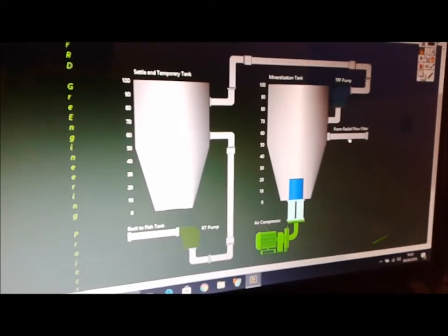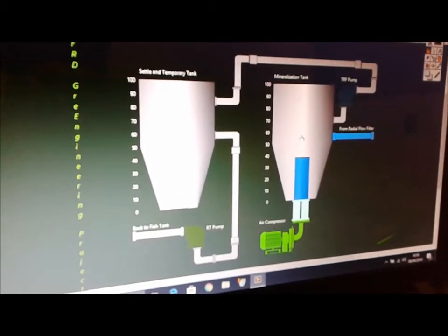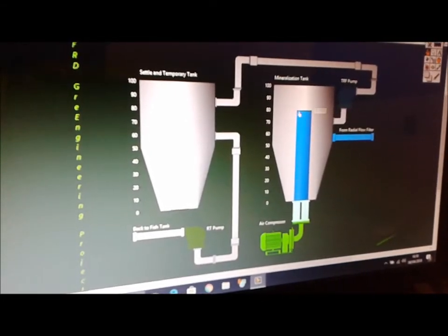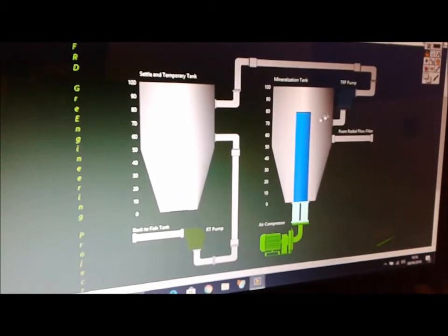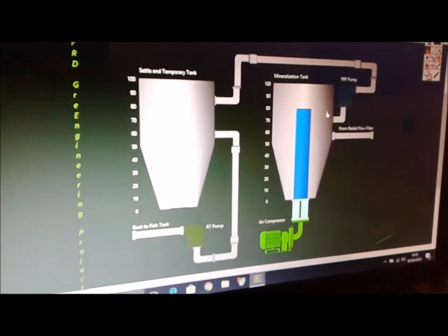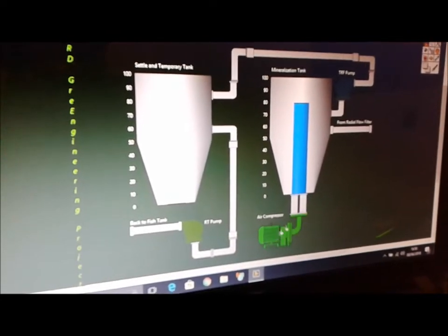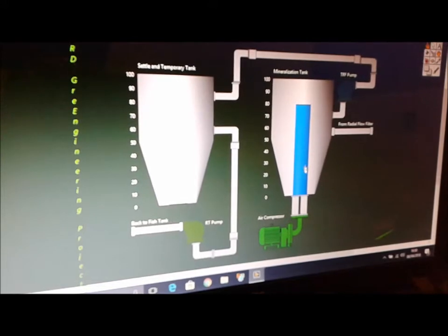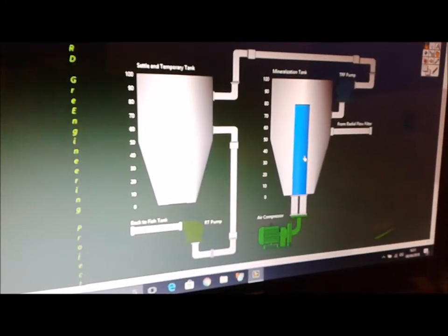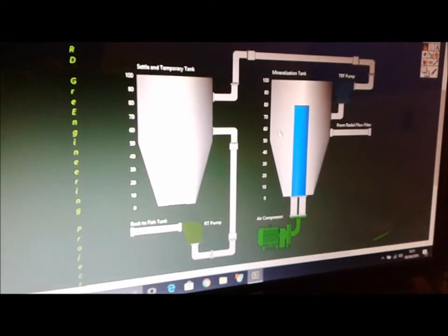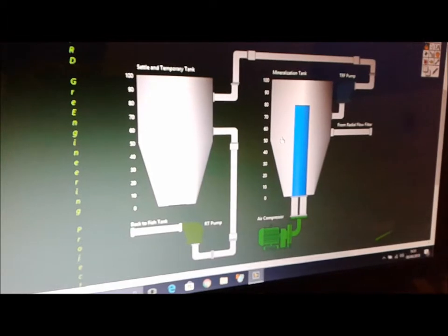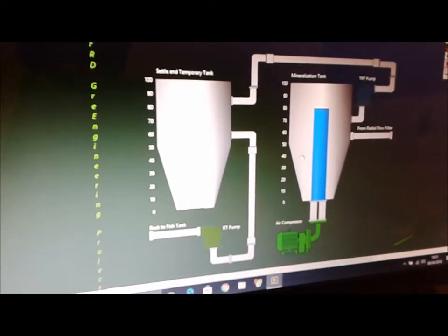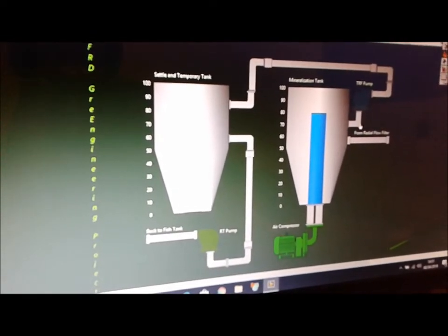Let's say that the radial flow filter shoots more water, more 40 liters. And this process continues until it reaches, let's say, 80 liters. Let's say that 80 liters is a threshold value for the controller. So after this threshold is reached, the controller can now turn off the air compressor so it momentarily stops the mineralization process so the solids can precipitate, can settle on the bottom of this mineralization tank. The controller now starts to monitor the turbidity using a turbidity sensor that's installed in here. When the turbidity goes down a bit, when the water is clear enough to be transferred, the transfer pump is turned on.